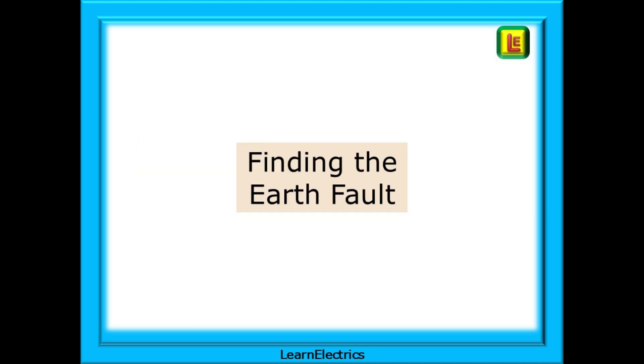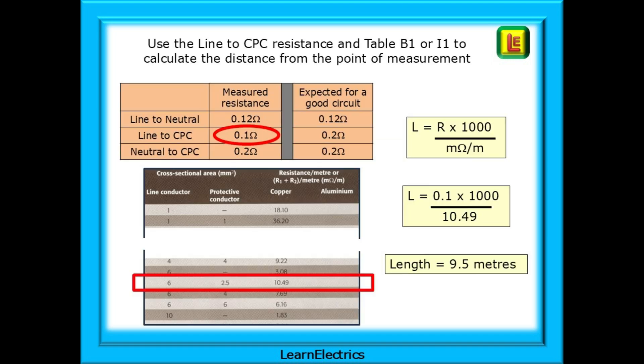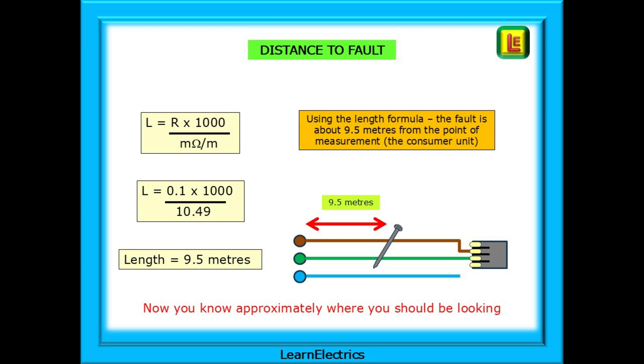Now we can move on to finding the approximate location of the fault. One method is to use the line to CPC resistance and table B1 or I1 to calculate the distance from the point of measurement, which is usually the consumer unit. Use the length formula and input the data into your calculator. With this example the length is calculated at about 9.5 metres from the consumer unit and should now be fairly easy to locate. This method is especially useful in industrial installations where cable runs may be many, many metres in length — it will get you into the right area close to the fault.